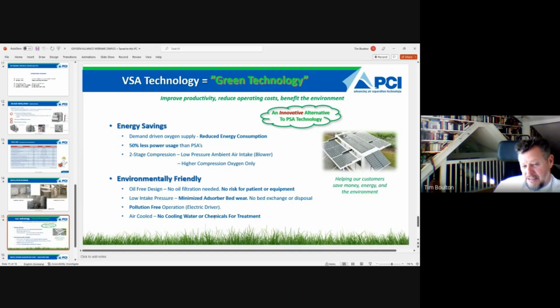So with the VSA two-stage system, you are only compressing up to the pressure that you need in your pipeline. You're only compressing the oxygen rather than the complete ambient air, which means it's a lot more power efficient. With these two-stage systems, you can also regulate the pressure according to your needs and probably altitude. Environmentally friendly.